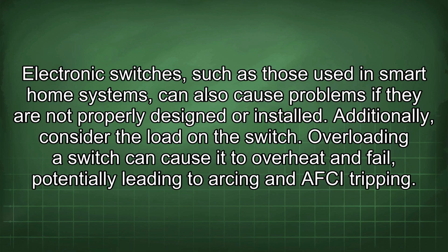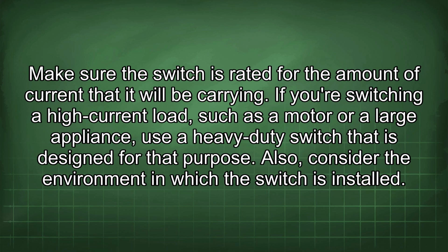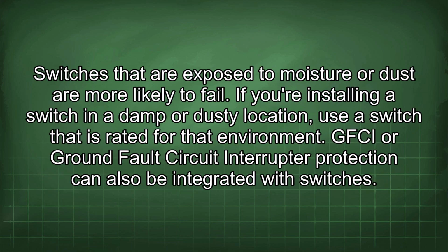Overloading a switch can cause it to overheat and fail, potentially leading to arcing and AFCI tripping. Make sure the switch is rated for the amount of current that it will be carrying. If you're switching a high current load, such as a motor or a large appliance, use a heavy-duty switch that is designed for that purpose. Also, consider the environment in which the switch is installed. Switches that are exposed to moisture or dust are more likely to fail. If you're installing a switch in a damp or dusty location, use a switch that is rated for that environment.